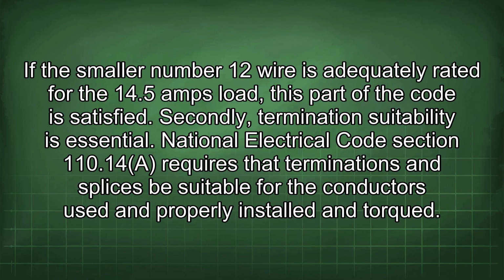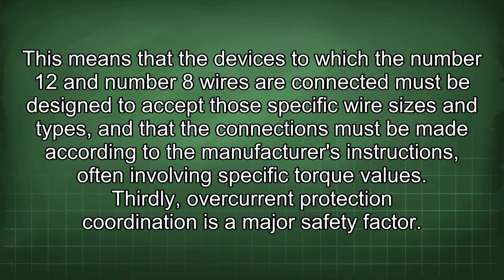National Electrical Code Section 110.14 requires that terminations and splices be suitable for the conductors used and properly installed and torqued. This means that the devices to which the number 12 and number 8 wires are connected must be designed to accept those specific wire sizes and types, and that the connections must be made according to the manufacturer's instructions, often involving specific torque values.